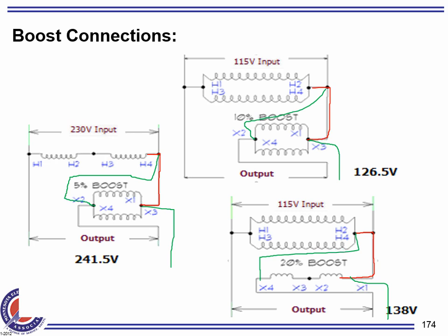By basically boosting the voltage. So what you do is, I want now, so this is 115. I want to remind you guys this is rated for 115. This is rated for 115. What happened when you series two coils? High voltage. Okay, now what if I need lower voltage? So look how we hook them up right here. You took the same coils that were sitting like this, and you just tied them at the end, right? That's your low voltage. Everybody can see that. This is your low voltage right in here. Then the same thing, and that's the only difference. So I can take 115 now and boost it up to 126.